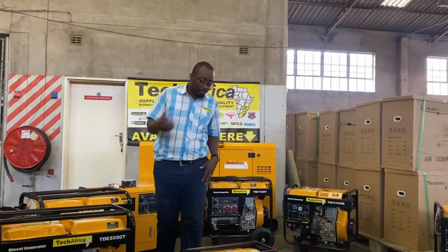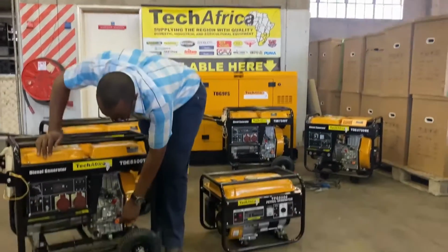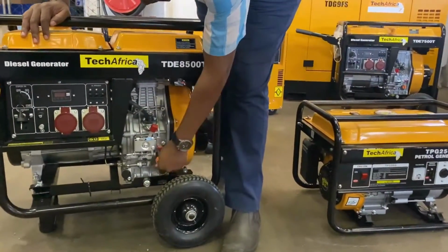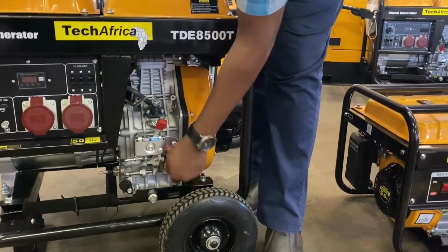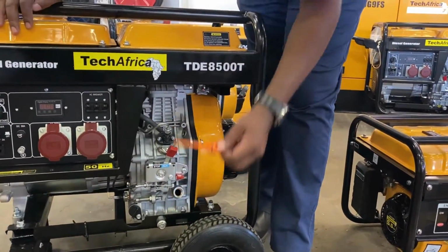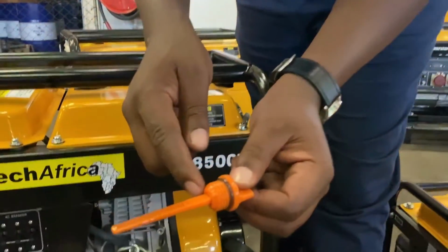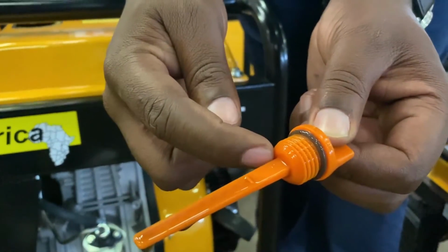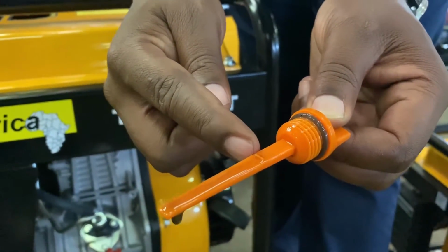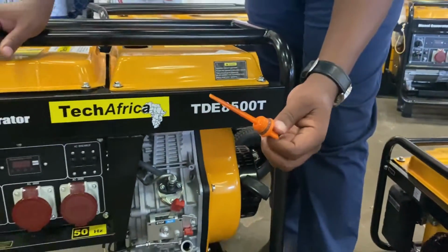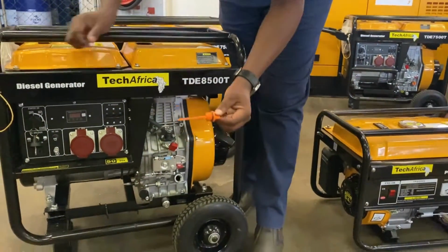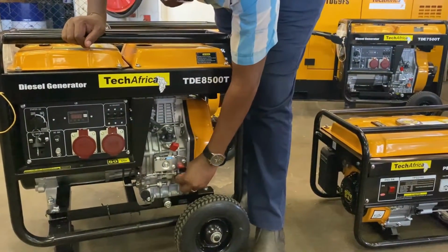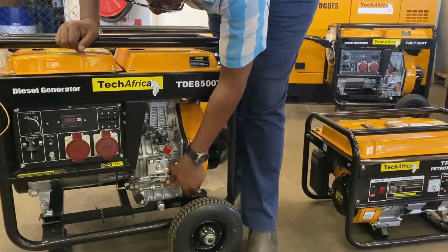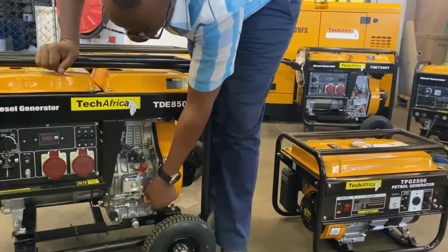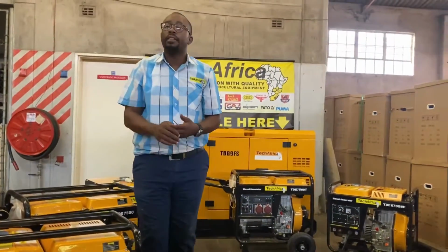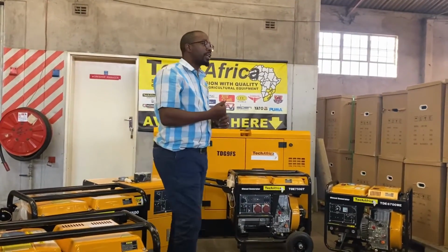Once you are putting your oil, this is your oil dipstick, and that's where you put your oil. As you can see, this one is full. You must not overfill it to the fullest - you only put oil up to the maximum line with 15W40 diesel oil. As you fill in the oil, you need to keep dipping to check your oil level, so you can gauge the amount of oil you're putting in the generator.